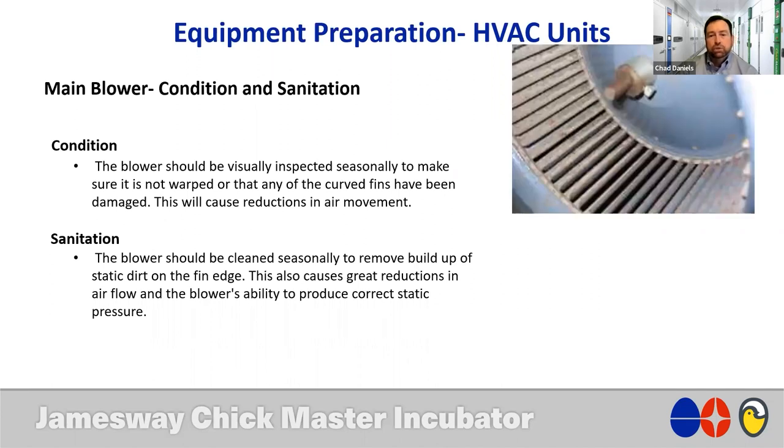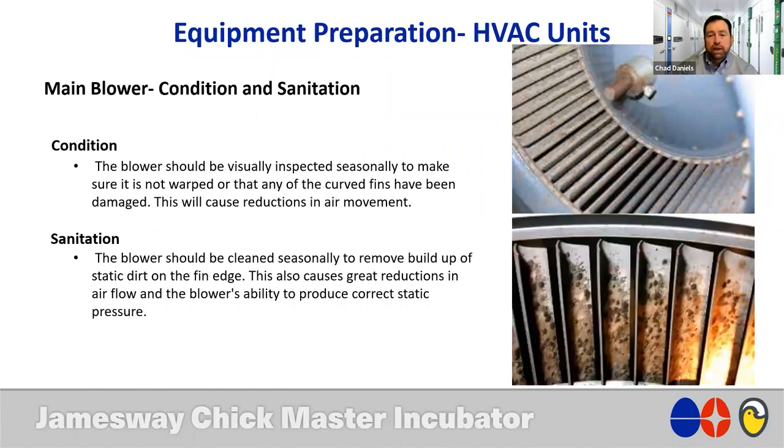When we look at sanitation, seasonally, these blowers should be cleaned. Because of the movement of the blower, it creates a static, and it will attract dirt and debris. You'll see buildup of that on the leading edge of the blower. And again, it just reduces the blower's ability to move air. Also, you'll see on the underside of the fins in a blower, you'll oftentimes have mold growth, or you'll have some dirt buildup in there as well. So it's always important to make sure these blowers are cleaned and prepared for your extreme season that's approaching.